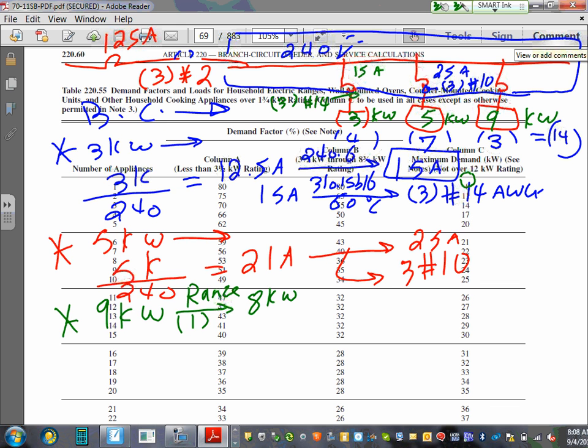For one range, you are allowed to use the table for branch circuits. Now remember, we finished sizing the feeder. We're sizing branch circuits now. For ranges, they allow you to use the table. Did you guys hear me? You're allowed to use the table. Who told me that? The bottom. Read at the bottom of the table. It tells you for one range, you're allowed to use the table.